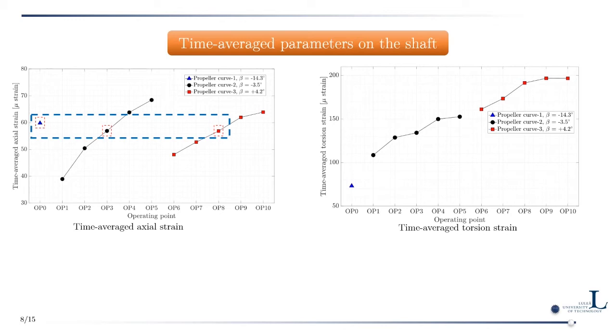Time average shaft parameters show that axial and torsion strain increase with turbine discharge for each propeller curve. Interestingly, axial strain at on-cam operating points (highlighted by red dashed boxes) is rather constant despite different guide vane openings and runner blade pitch angles. Bending strain in both X and Y directions generally increases with guide vane opening.